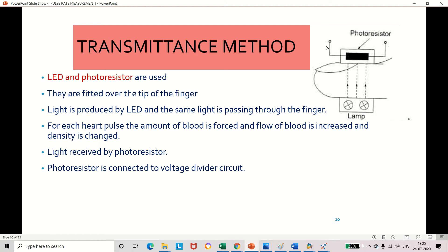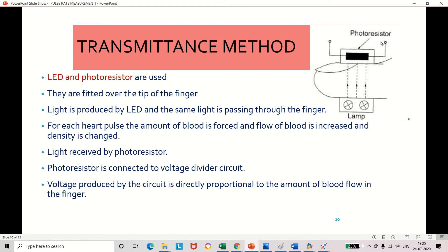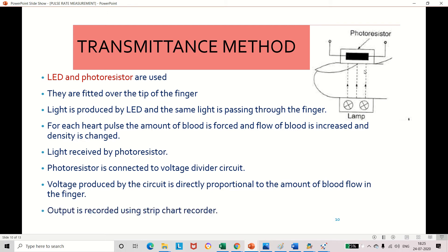To summarize the transmittance method: we use an LED and photoresistor fixed over the fingertip. Light from the LED passes through the finger and falls on the photoresistor on the other side, changing its resistance. A voltage divider circuit is connected, and the voltage produced in the circuit is proportional to the amount of blood flow in the fingertip. We can record this pulse rate using a strip chart recorder.